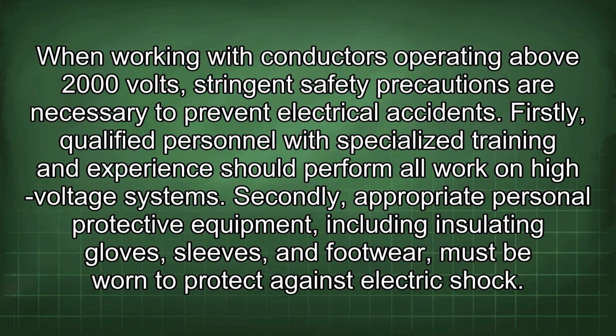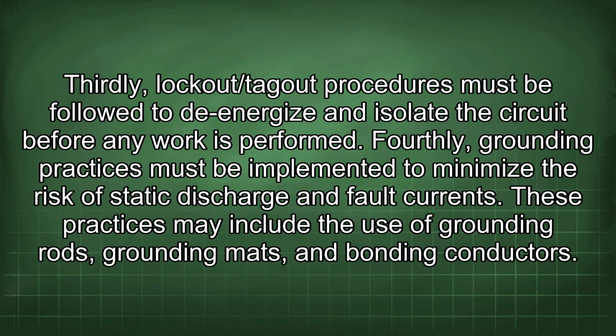When working with conductors operating above 2000 volts, stringent safety precautions are necessary to prevent electrical accidents. Firstly, qualified personnel with specialized training and experience should perform all work on high voltage systems. Secondly, appropriate personal protective equipment, including insulating gloves, sleeves, and footwear, must be worn to protect against electric shock. Thirdly, lockout/tagout procedures must be followed to de-energize and isolate the circuit before any work is performed. Fourthly, grounding practices must be implemented to minimize the risk of static discharge and fault currents. These practices may include the use of grounding rods, grounding mats, and bonding conductors.